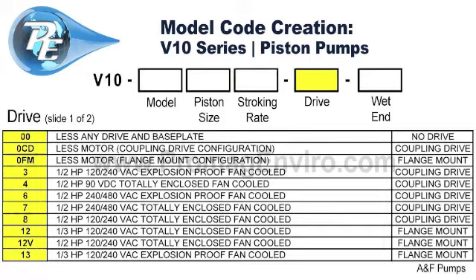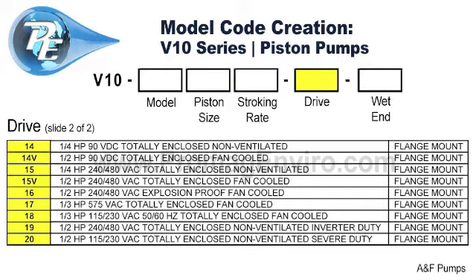This is slide number 2 of 2 for the drive model code. The number 14 represents quarter horsepower, 90 volt DC, totally enclosed, non-ventilated flange mount. 14V represents half horsepower, 90 volt DC, totally enclosed, fan cooled flange mount. The number 15 represents quarter horsepower, 240, 480 volt, totally enclosed, non-ventilated flange mount. 15V represents half horsepower, 240, 480 volt, totally enclosed, fan cooled flange mount.